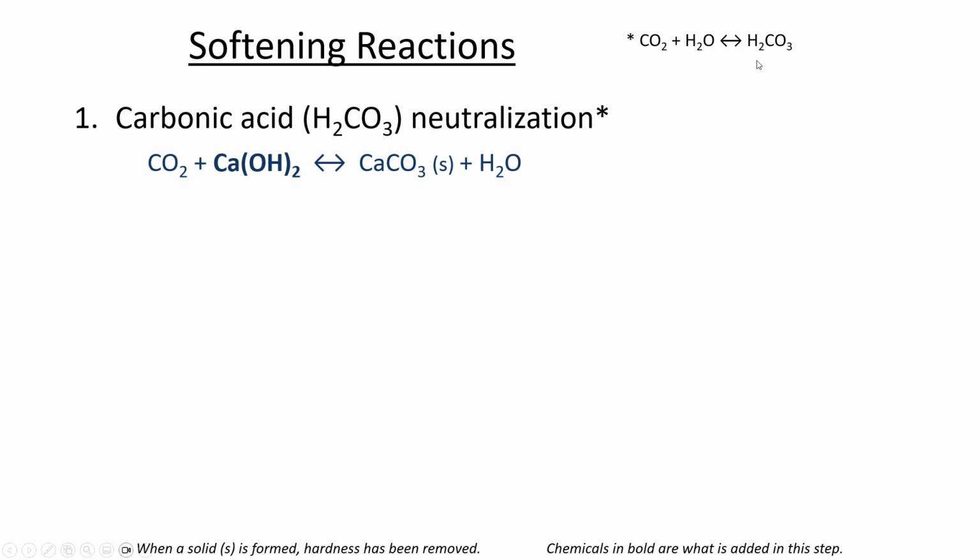There's not a lot of it, and it doesn't have a huge effect, but still, when you add the lime to water, a portion of it is going to be burned up just neutralizing that carbonic acid in the water. So that's the first thing that we have to overcome, and this is not going to cause any softening effect. You're losing a little bit of your lime up front just to neutralize the acid that's in the water because of equilibrium with atmospheric carbon dioxide.